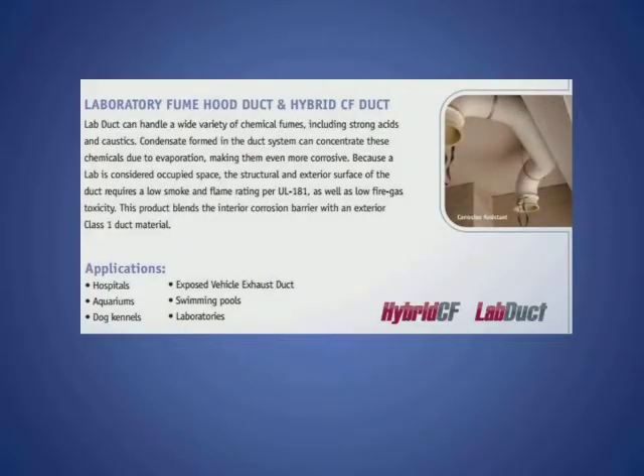The laboratory fume hood duct, or hybrid CF, it's corrosion fire, was developed for occupied space, but if you consider the application, a laboratory fume hood may be generating strong acid fumes. The acid fumes, or caustic fumes, have a tendency to condense in ductwork and become even more corrosive. So it's very important to have a corrosion-resistant interior. And if it's a building where people are working or school students are there, you need to have the Class 1 duct exterior in case there's ever a fire. So that's the reason for developing the laboratory duct or hybrid CF.